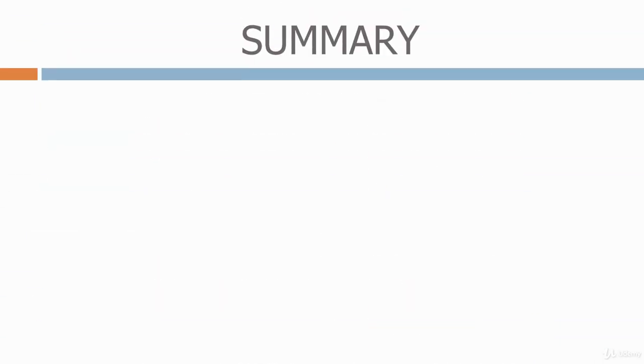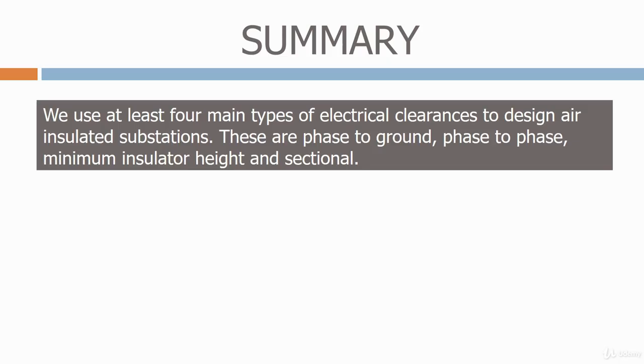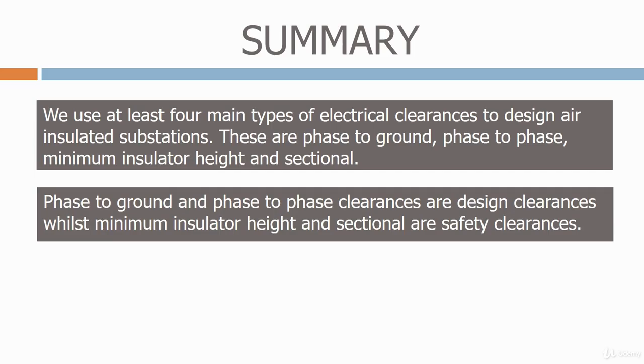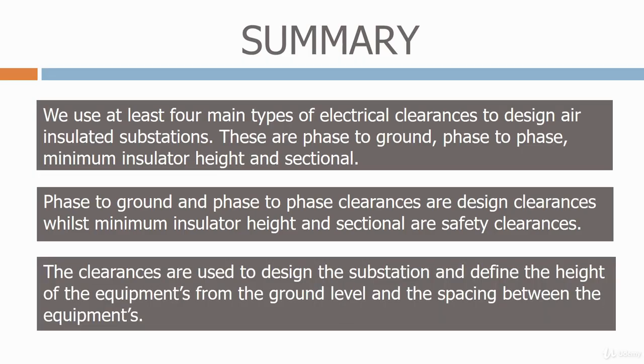Let's summarize what we learned today. We use at least 4 main types of electrical clearances to design air-insulated substations. These are phase-to-ground, phase-to-phase, minimum insulator height, and sectional. Phase-to-ground and phase-to-phase clearances are design clearances, whilst minimum insulator height and sectional are safety clearances. The clearances are used to design the substation and define the height of the equipment from the ground level and the spacing between the equipment.